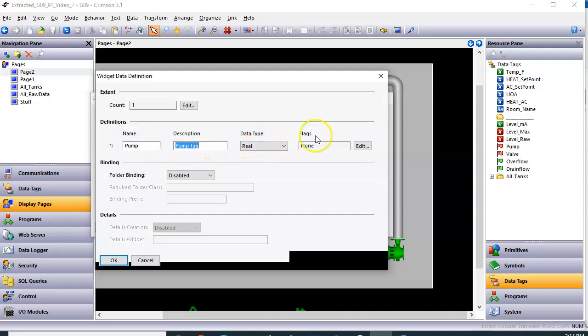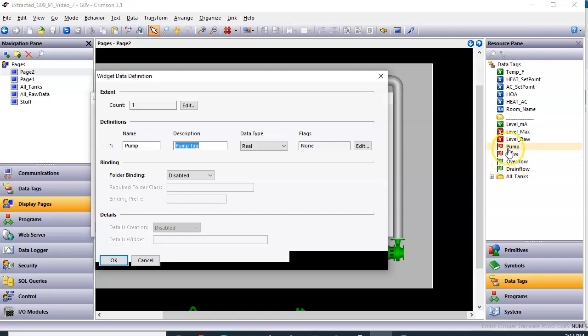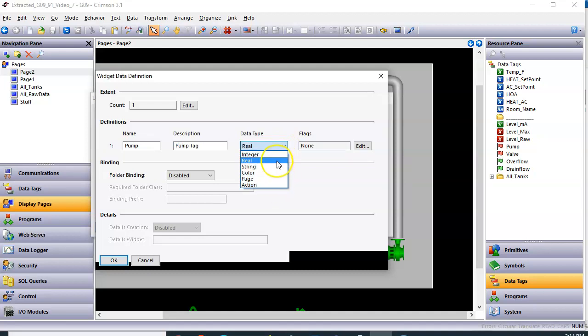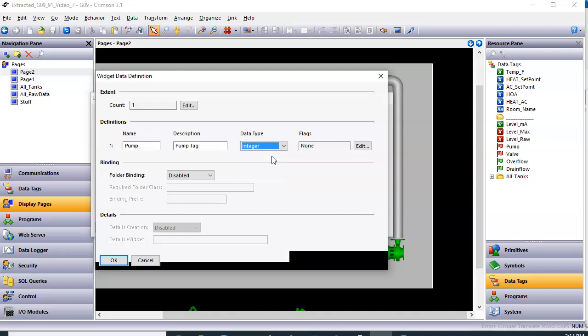When we declared the tags, any of the flag tags are booleans. They're on off booleans. Anything with that X is an integer. A pi is a floating point or real number. So if you look here in the data type, when I hit the pull down, I don't see an option to pick a bool type here. That's because the boolean on off is part of the integer family. So I'll select integer.